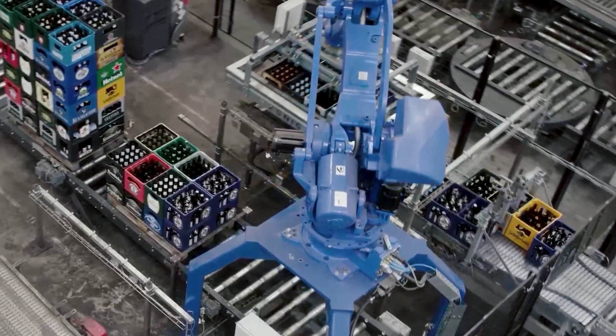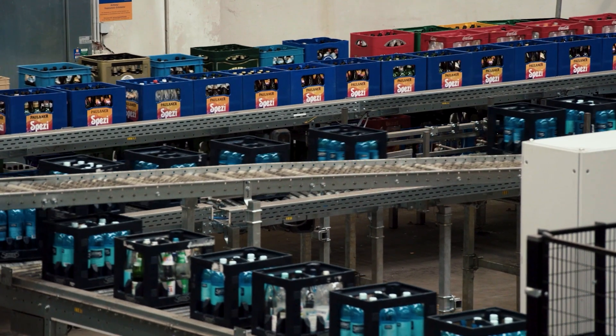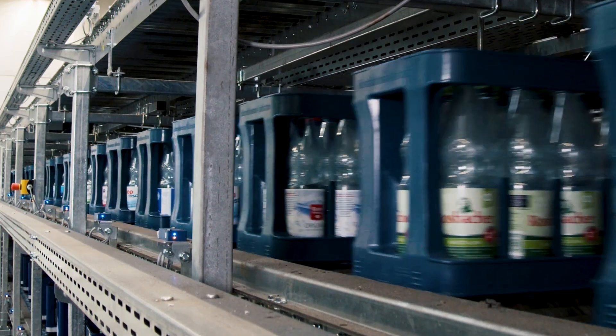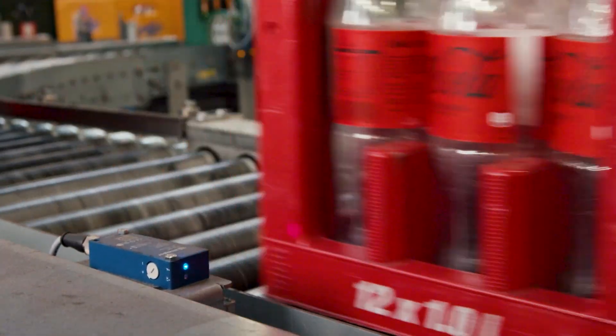After a completeness check and sorting by manufacturer, the boxes are transported to final processing via further conveyor lines. The presence of the crates is tracked at each meter. We mainly use normal light barriers for crate detection. With many other manufacturers, we have problems with the fact that they react to certain logos from the various beverage producers. Because Wenglor's sensor system can be adjusted, we can master this really well and it offers the additional extremely useful feature that it can also work with an oblique angle.